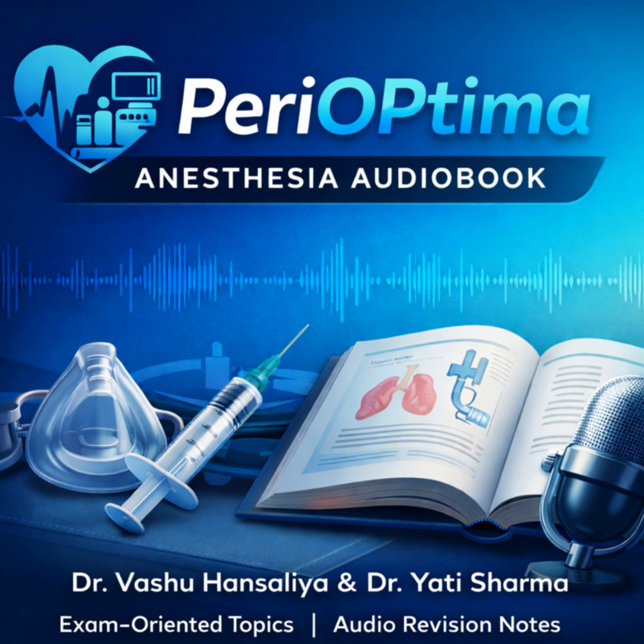And the modern one? The modern standard is the pre-vacuum or high-speed vacuum-assisted autoclave. In this type, a powerful vacuum pump sucks almost all the air out of the chamber before any steam is introduced. So that solves the air pocket problem. It solves it completely. When the steam is then injected, it instantly penetrates the entire load, even the densest of linen packs. This makes the cycles much faster and more reliable.